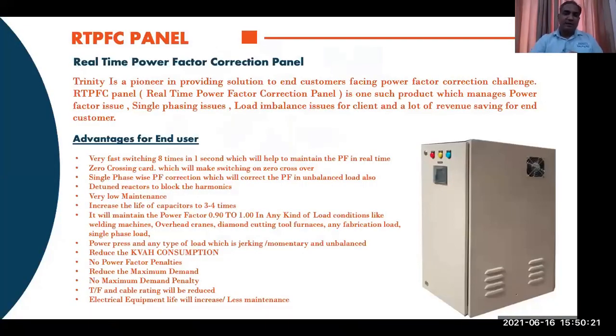In this panel, we can do switching 8 times in 1 second for any kind of load, and there are zero crossing cards, so wear and tear is very low. The only replacement we see once a year is a relay card that might have failed or some component that burned out. Otherwise there's no replacement of any components at all. Wear and tear is minimal, and PF is properly maintained.